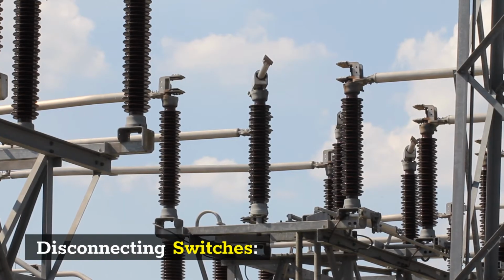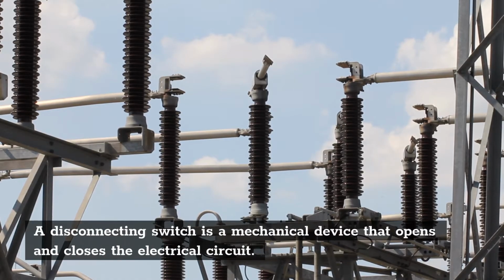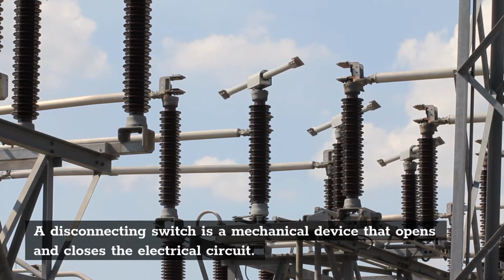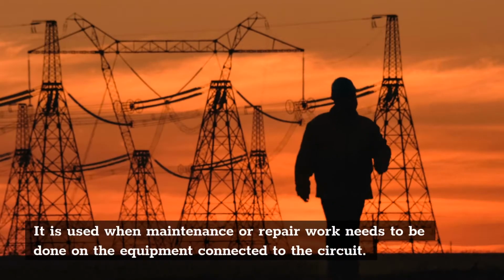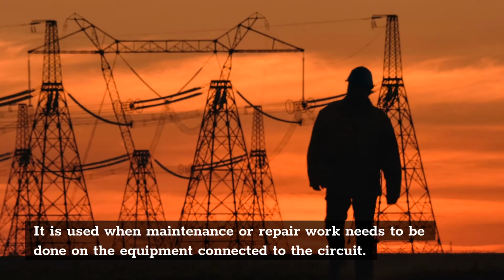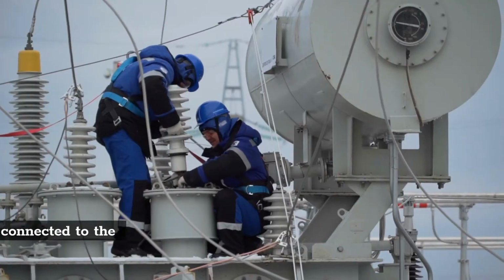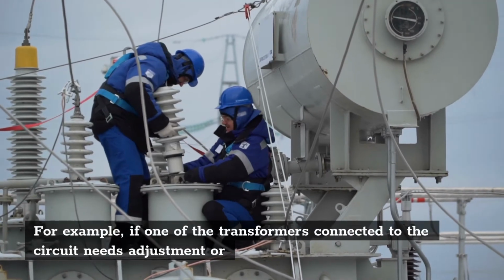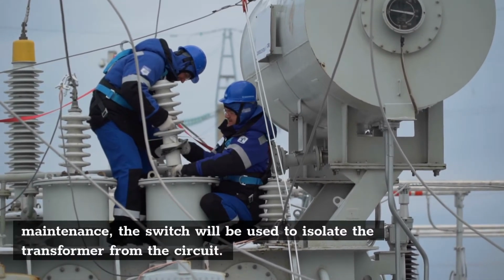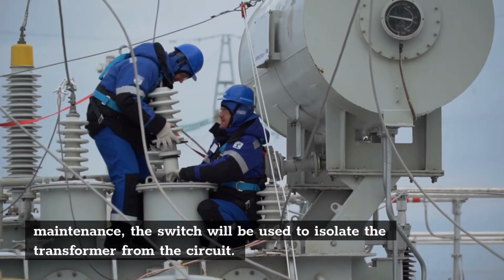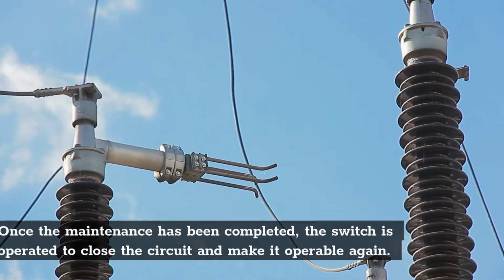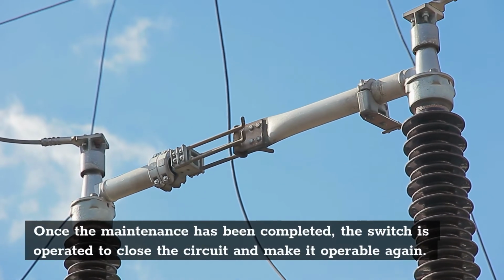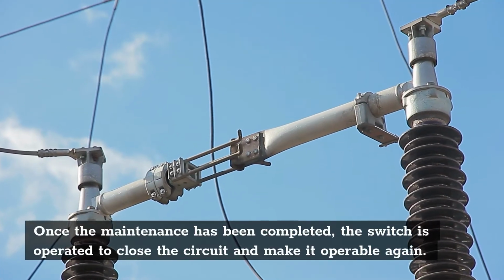Disconnecting switches. A disconnecting switch is a mechanical device that opens and closes the electrical circuit. It is used when maintenance or repair work needs to be done on the equipment connected to the circuit. For example, if one of the transformers connected to the circuit needs adjustment or maintenance, the switch will be used to isolate the transformer from the circuit. Once the maintenance has been completed, the switch is operated to close the circuit and make it operable again.